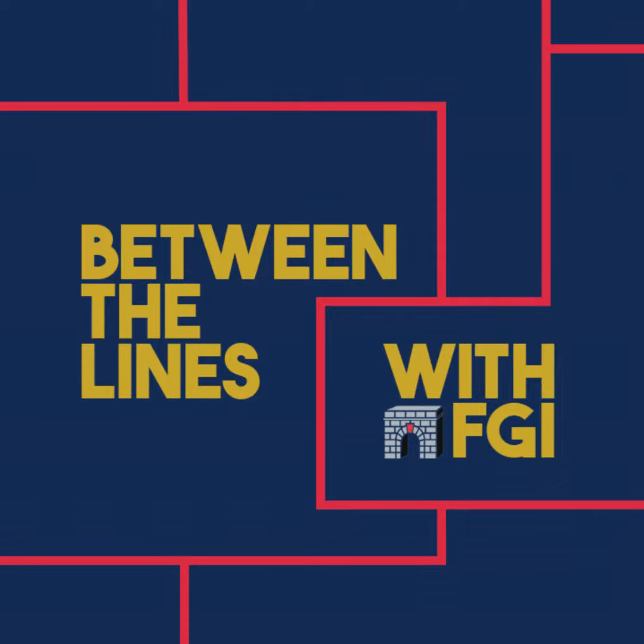There have been problems that I've seen where engineers essentially mix and match, right? We're going to use the GE quench pipe discharge detail because the last MRI project we did was a GE one, and we have that in CAD, and we can copy and paste it, and we'll use it for a Philips MRI scanner, even if the design and engineering criteria don't match. Problematic? It can be, depending. If you're taking a less conservative design and putting it on a system needing a more conservative one, yeah, that can be problematic.